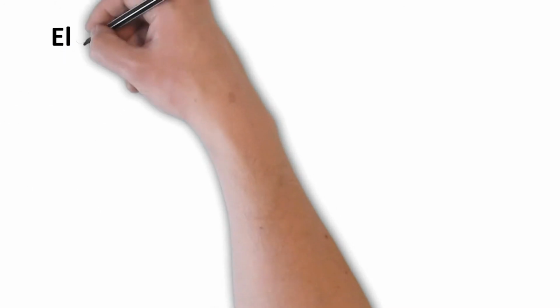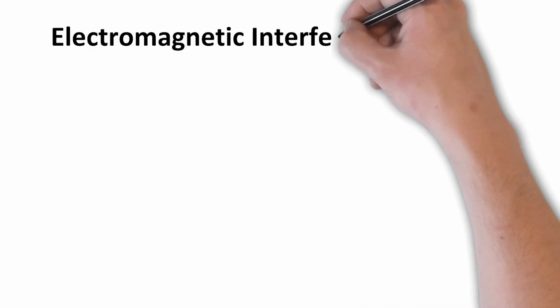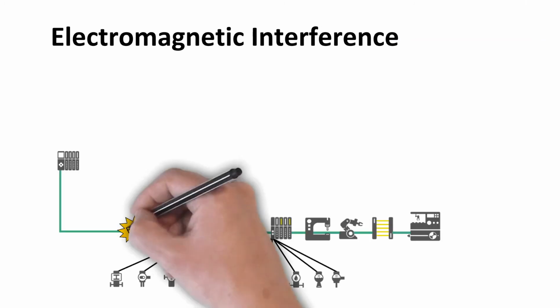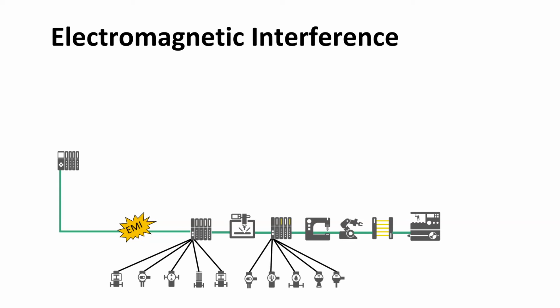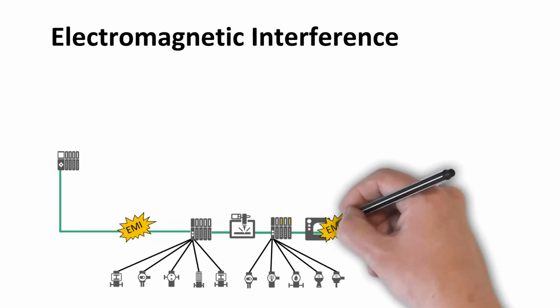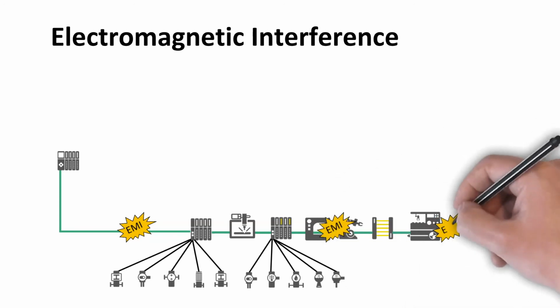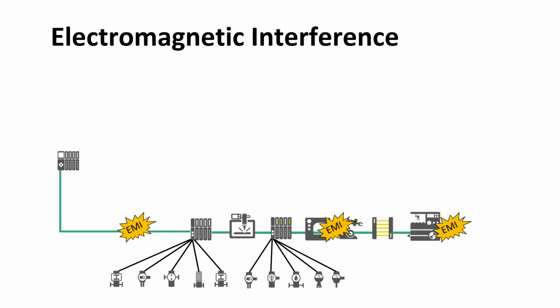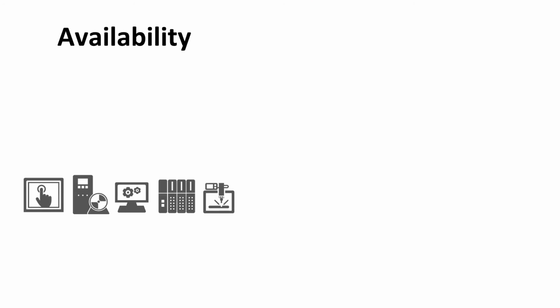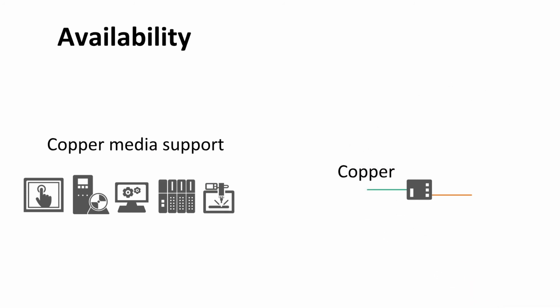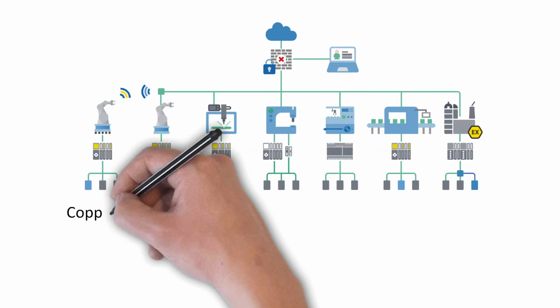Electromagnetic interference. Because copper cables operate through electrical signals, they can be prone to the effects of electromagnetic interference. This is why you must be careful when running power cables and data cables close to each other. Also, VFDs and other industrial equipment can be significant sources of EMI. Fiber optic cables cannot be affected by external magnetic fields as they are immune to EMI. Availability. Most devices in an industrial network have built-in connections that support copper media. You can employ a media converter to make the transition to fiber, but it is an extra step to keep in mind. In summary, you can employ standard copper or fiber Ethernet cables in Profinet networks.